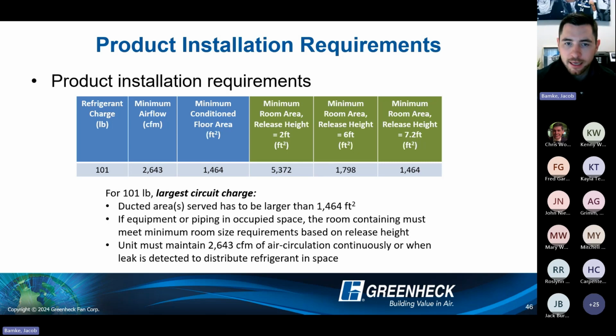So it's dependent on release height. Where is the lowest amount that refrigerant could be released from the floor? There are additional room area requirements if you want to install that into that space. In this example, if you had a connection at 2 feet or less, it would go up to 5,372 minimum square feet. And then for overall minimum airflow, the unit must maintain 2,643 CFM in this example of that air circulation strategy when a leak is detected, to distribute into that space.